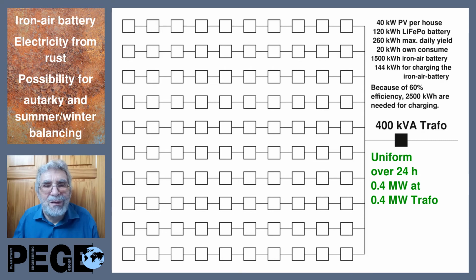In this case, we charge the iron-air battery with 144 kilowatt hours, and when the whole village does the same, we have 0.4 megawatt delivered, and the Trafo has 0.4 megawatt. Now it works without grid extension. This is the value of the iron-air battery, that we have here no grid extension. And what we do with the stored energy, we will deliver it in winter time.